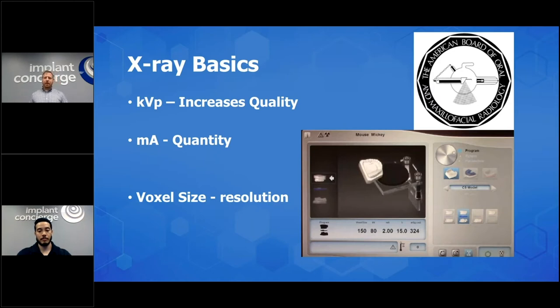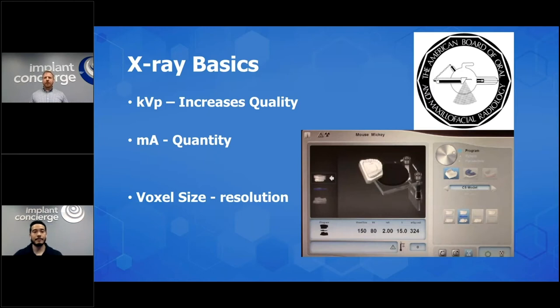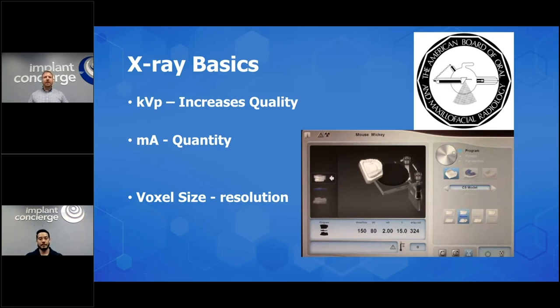When it comes to KVP and MA, I'm not going to talk about the physics behind it, but basically these numbers can be adjusted on pretty much all machines. Description is a clinical situation where if you have two patients — one has a lot of restorations, we're talking about implants, amalgam, PFMs — versus a patient that has none of that. When you hit the button and the KVP and MA is already pre-decided, that patient with a lot of restorations is going to have a lot of scatter, a lot of beam hardening. Just changing those numbers a little bit, you're going to get a much better image.